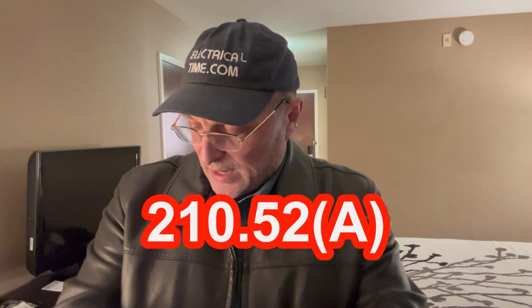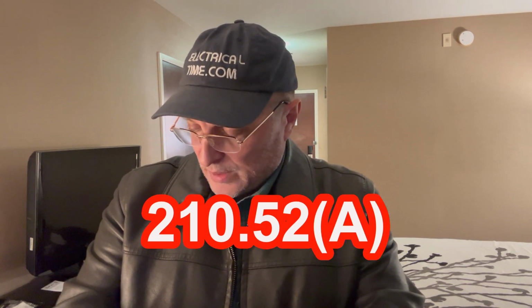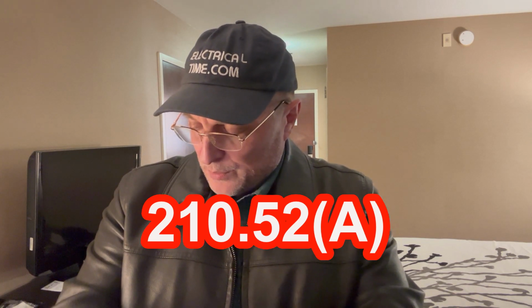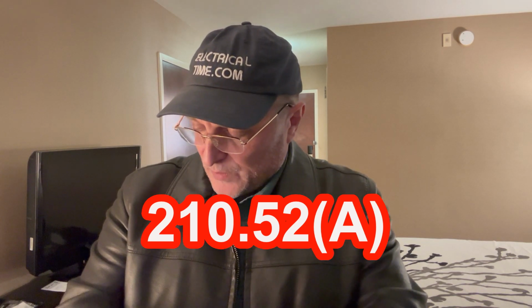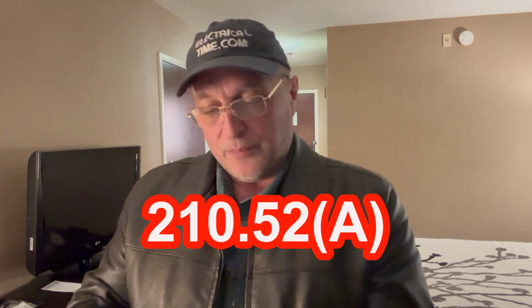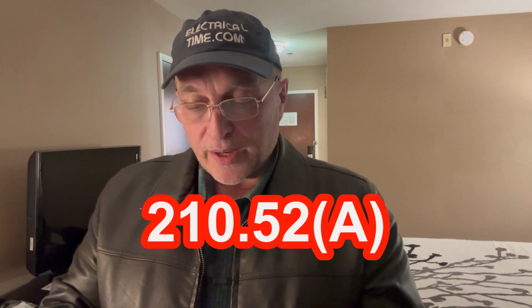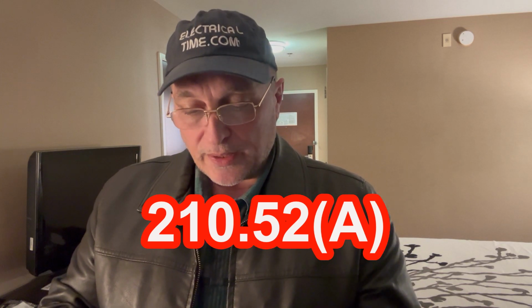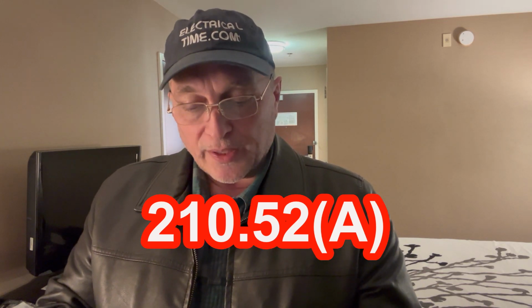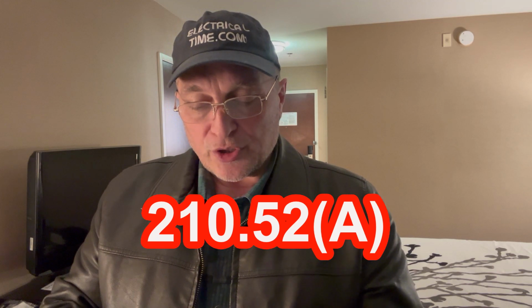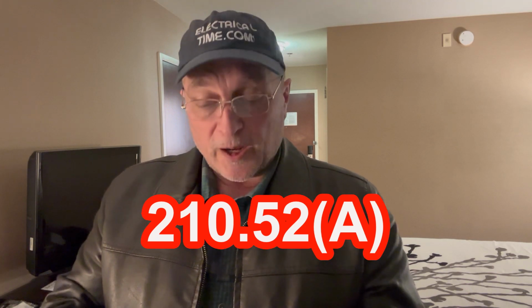It says in every kitchen, family room, dining room, living room, parlor, library, den, sunroom, bedroom, recreation room, or similar room or area of a dwelling unit, receptacle outlets shall be installed in accordance with the general provisions specified in 210.52A1 through A4.